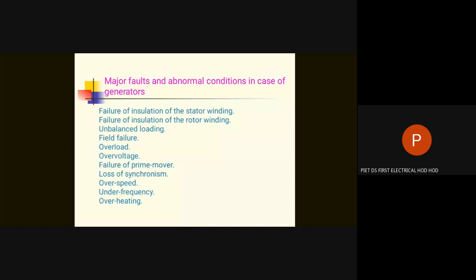field failure, that means failure of the field of the generator which is connected to the bus. If the generator is overloaded, if there is an overvoltage in the generator, if the prime mover of the generator fails, then if synchronism is lost, if there is overspeeding, if the frequency of the whole system comes down or goes up. Underfrequency particularly is for the frequency coming down. Then overheating, if the generator winding is overheated. So these are the major faults and abnormal conditions in case of a generator.